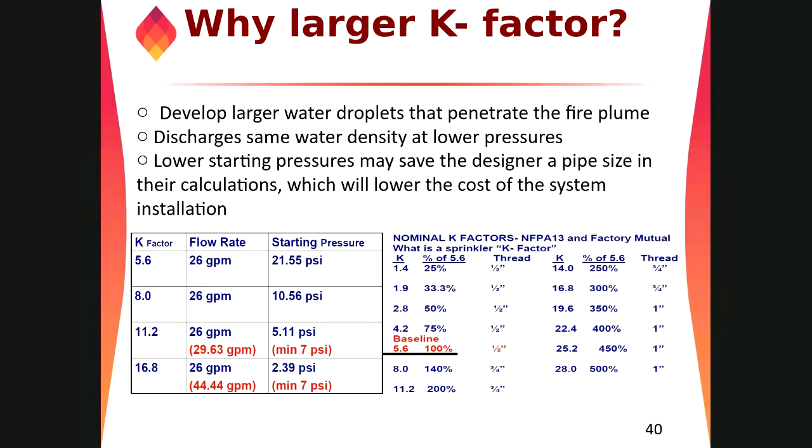No, actually, when you are performing hydraulic calculation in the software, the software will ask how many sprinklers you are going to open. Those open sprinklers need to be provided the K factor. There is some setting in the software where we have to select the K factor values.